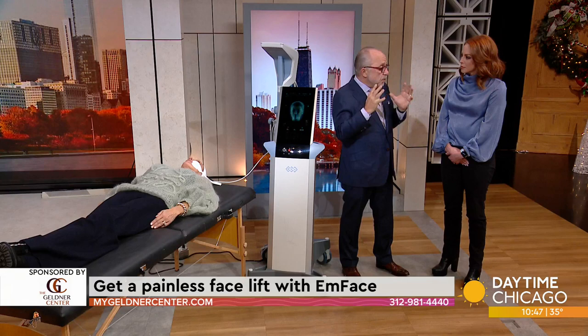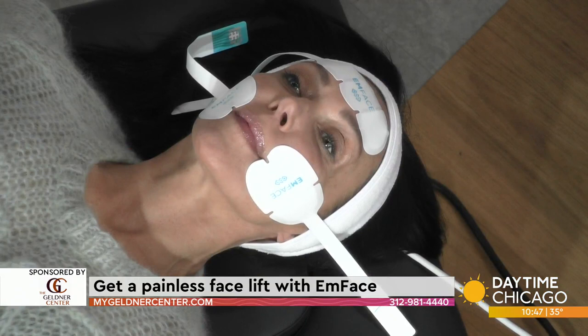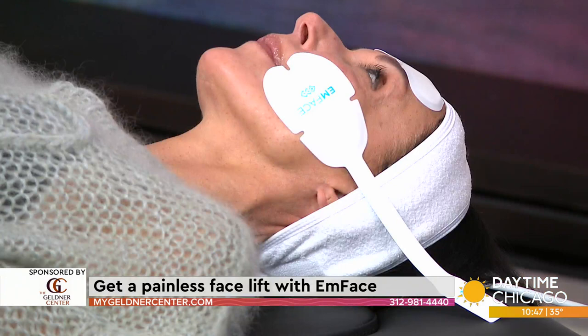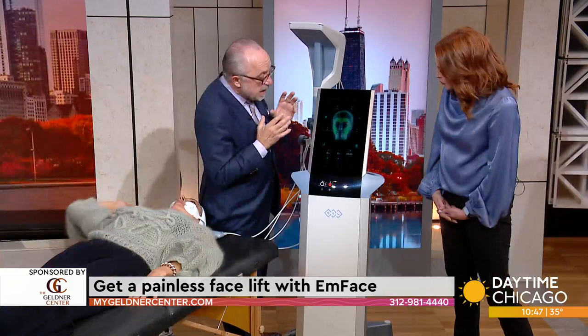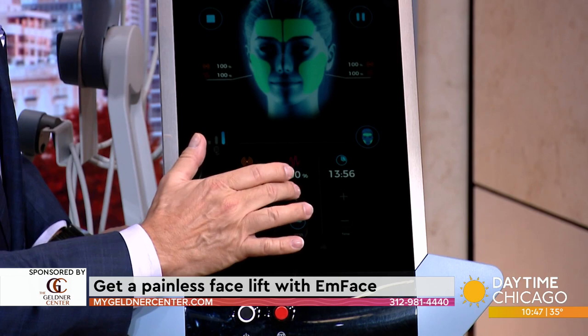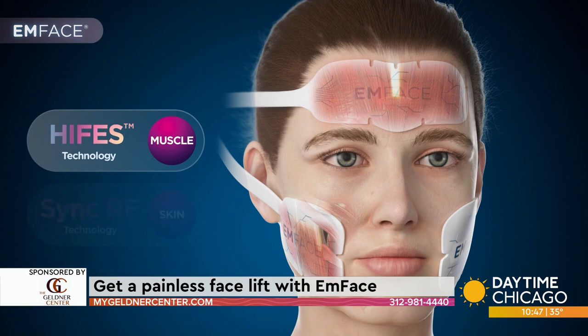This is a wonderful technology that has really proven itself over time by BTL. So let's take a look — Oksana here is already prepared. Using these devices, we hook this up to the equipment. All of the electrodes are attached, the grounding pad is attached, and now we set up exactly what we want to do. I can control the amount of energy that we're delivering to these areas — radiofrequency as well as HIFES, which is the electrical stimulation.